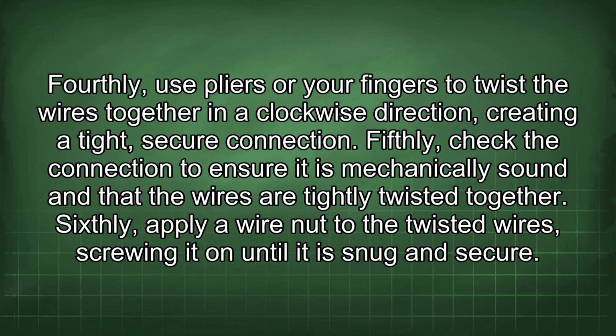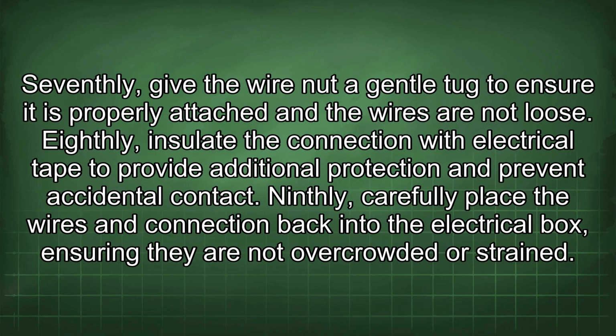Fifthly, check the connection to ensure it is mechanically sound and that the wires are tightly twisted together. Sixthly, apply a wire nut to the twisted wires, screwing it on until it is snug and secure. Seventhly, give the wire nut a gentle tug to ensure it is properly attached and the wires are not loose.